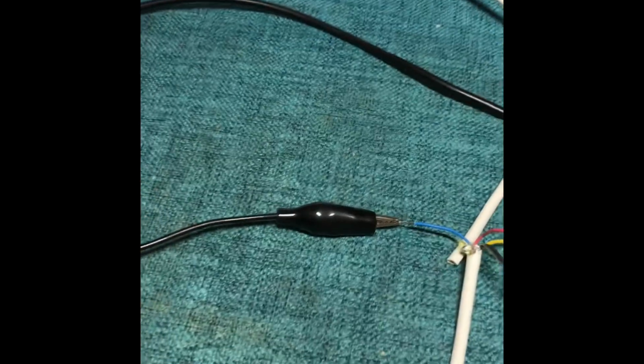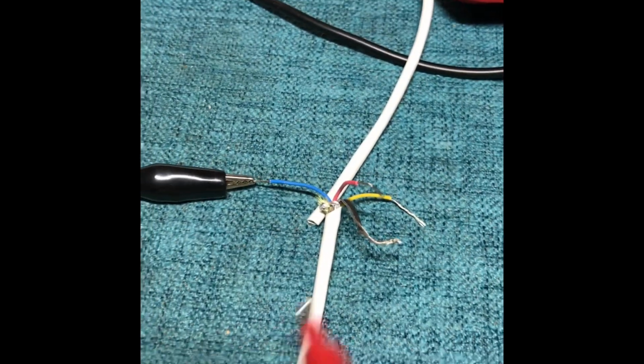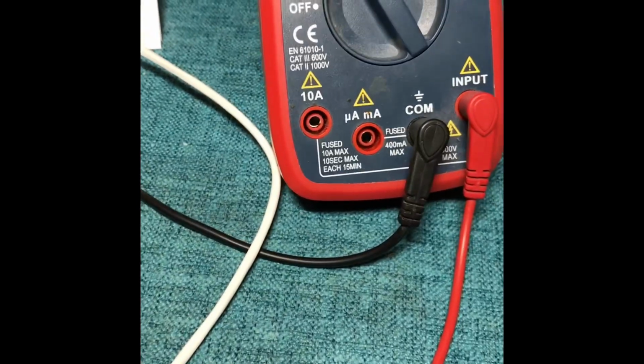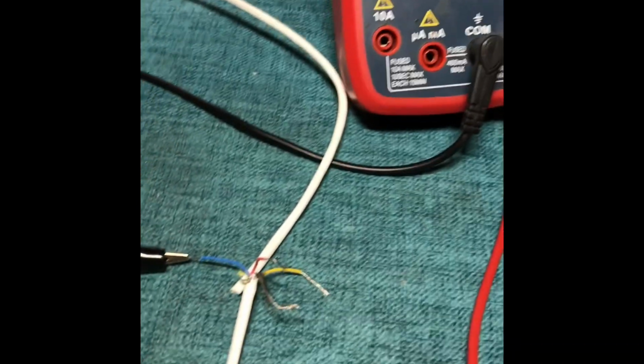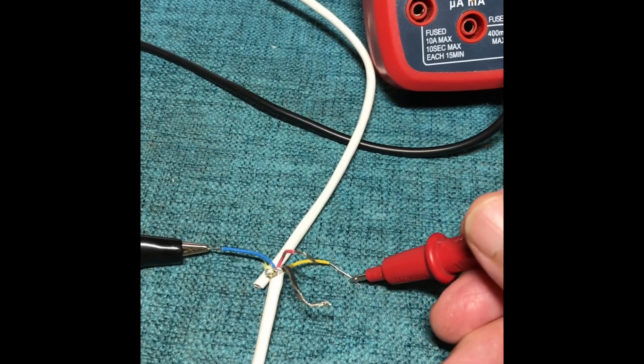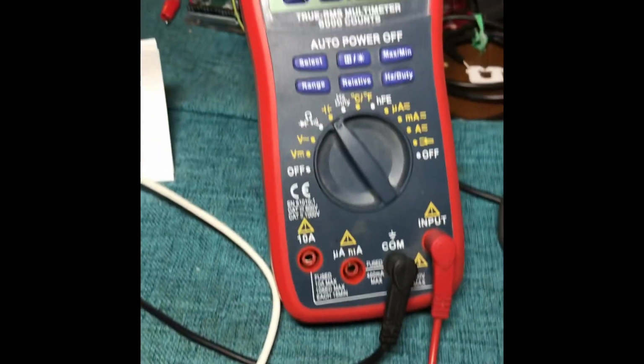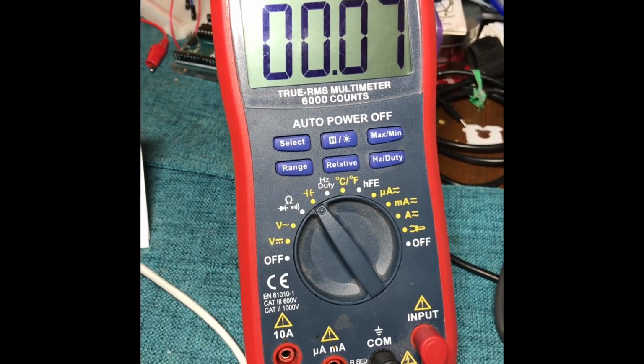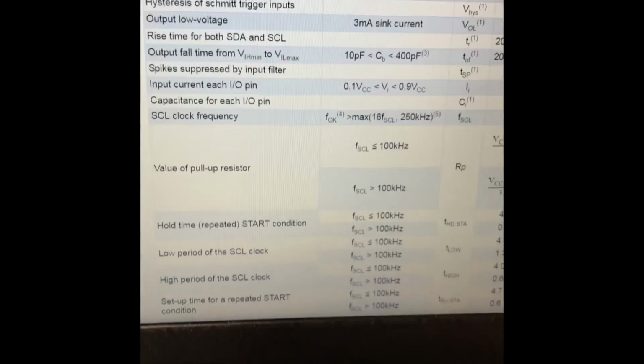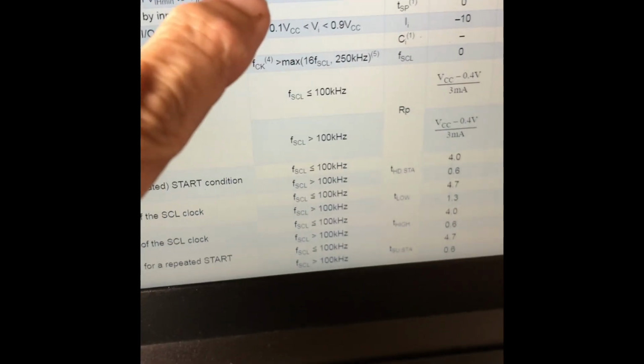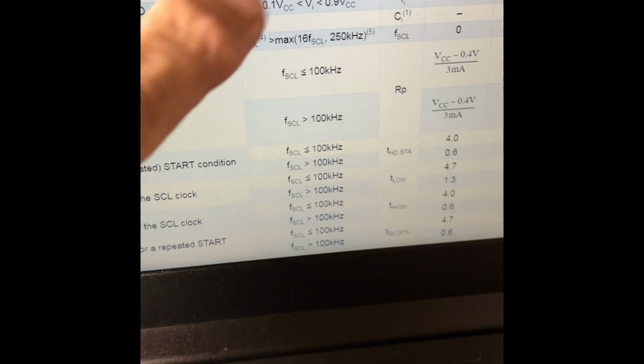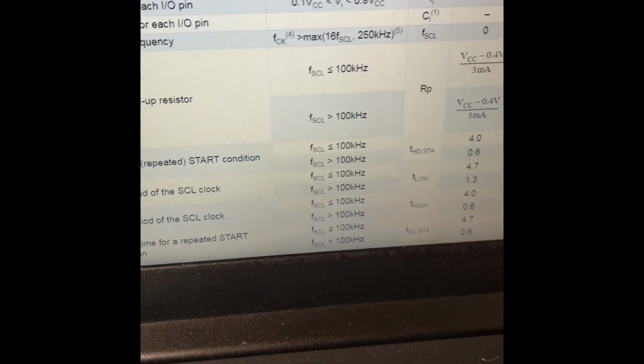So we've got the data line connected to the black cable coming from the multimeter, and the red cable we're going to touch to the clock line, and we're getting a value of 7 hundredths of a nanofarad. That's 70 picofarads, and the requirement on the cable capacitance is that it be greater than 10 picofarads and less than 400 picofarads. So our 70 picofarad cable falls within that limit.